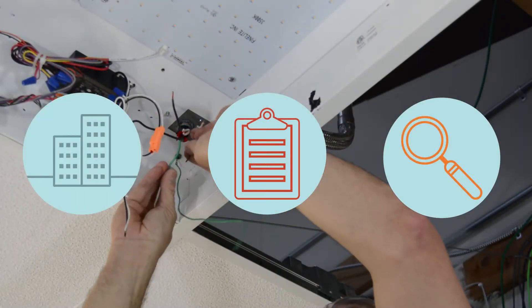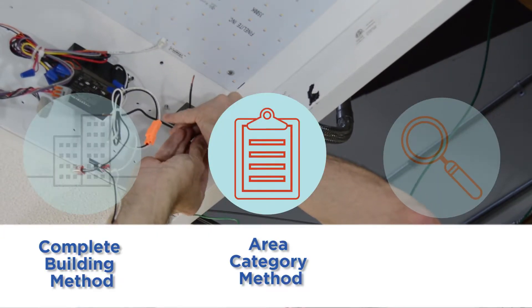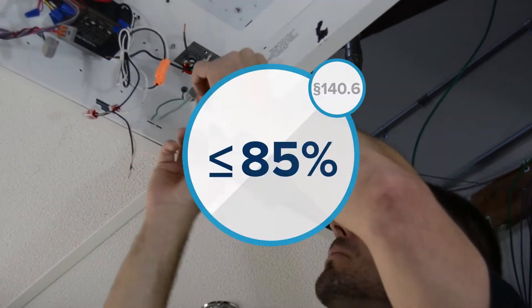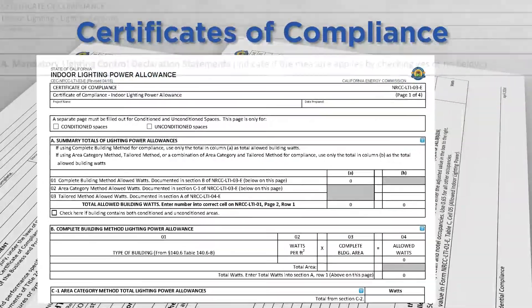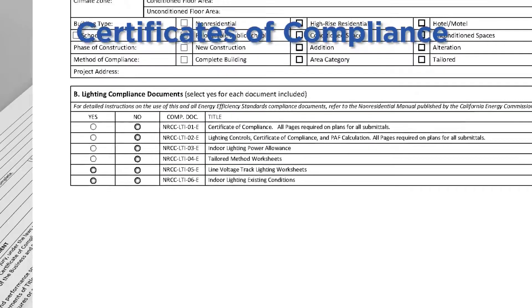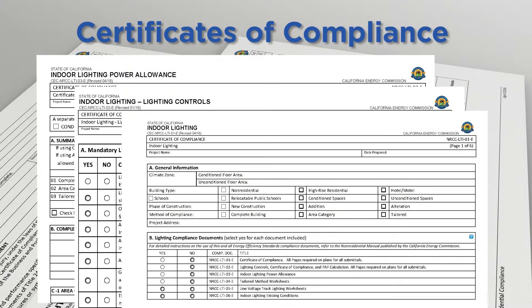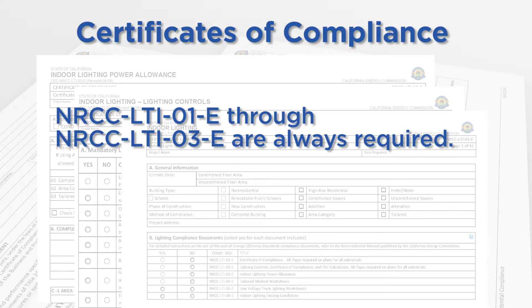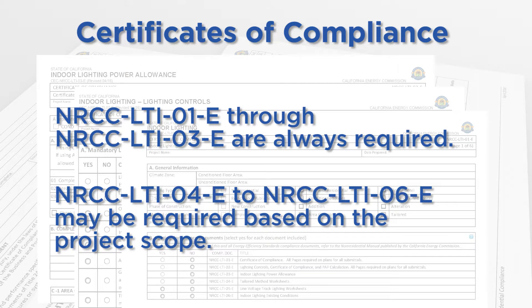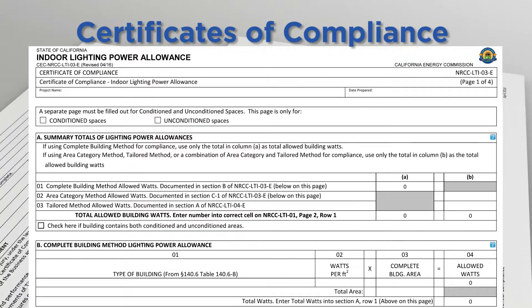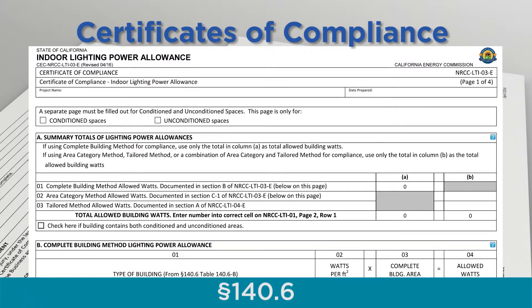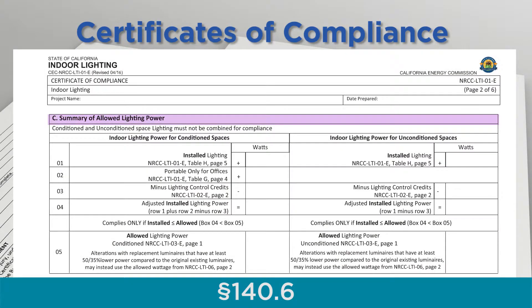For this compliance option, the lighting power allowance must be calculated using either the complete building method, area category method, or tailored method. The proposed retrofit must deliver a lighting power that is 85% or less than allowed under section 140.6. For these projects, fill out the applicable certificate of compliance forms LTI-01, LTI-02, and LTI-03. These forms document lighting power allowance, proposed lighting, and proposed controls. Forms LTI-04 through LTI-06 may also be required depending on the project scope. Use Table H on LTI-01 to record information on the replacement luminaires, newly installed luminaires, altered luminaires, and luminaires with component modifications. Use LTI-03 to determine lighting power allowance specified under section 140.6 and use Table C of LTI-01 to determine the 85% allowance.